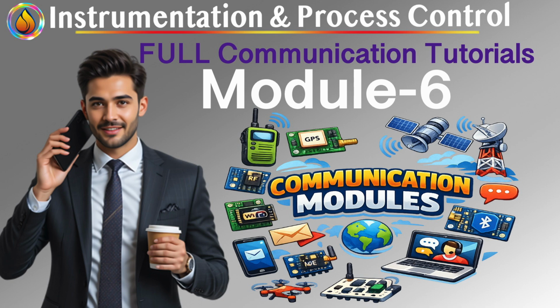Byte-oriented networks, when devices become smart. Now, step one level up. Byte-oriented networks exist because many field devices are more than binary, but not full-blown control systems. Here, devices exchange multiple parameters, status words, commands, measured values. We're talking bytes, not bits. Typical devices include motor starters, variable speed drives, barcode readers, pressure and temperature transmitters, analyzers.